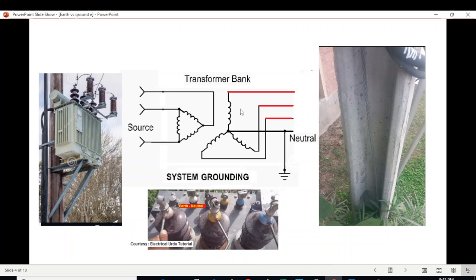Okay, now let me explain a little bit on the transformer side. You know, the transformer in the domestic supply in Pakistan especially, the input is 11 kV and the output is 220 volt. Now, these are three wires, input side, three wires, and this is the top of the transformer. So they are connected in the bigger terminals here, and they are blue, yellow, and red. So three wires is the input, but the output is four wire. And how do we get four wire? It is from delta, this side is star connection. So the neutral point is another wire.